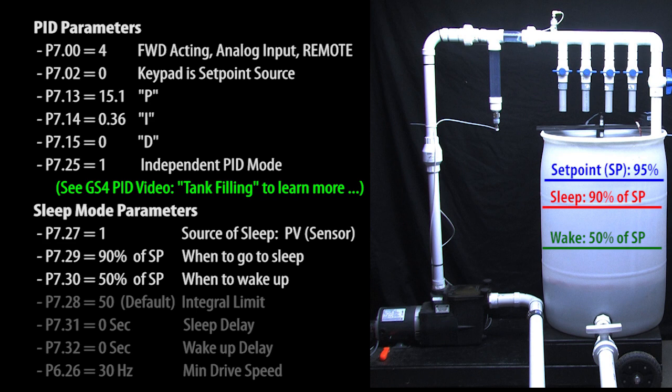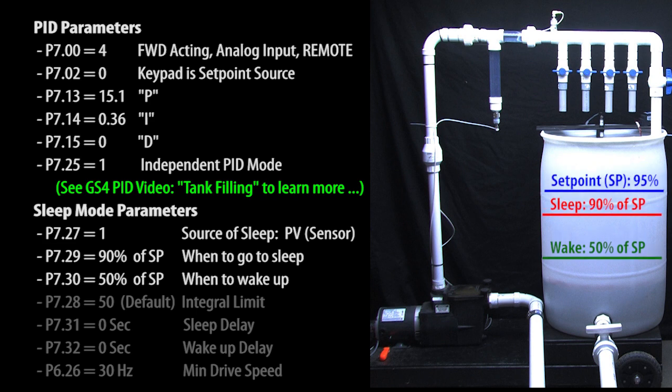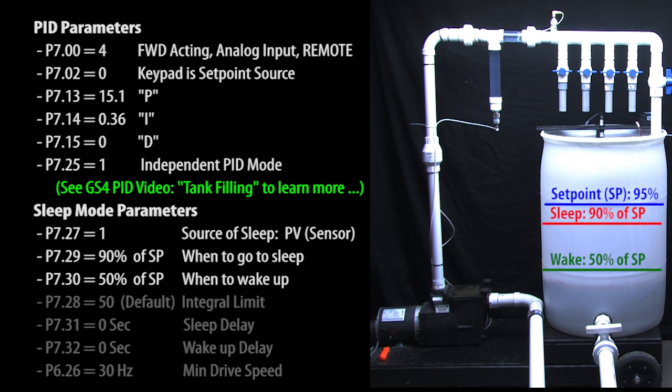Now that's really cool because if we change the set point, the sleep and wake levels will automatically adjust relative to that new set point. Which means we don't have to adjust the sleep and wake levels each time we change the set point.